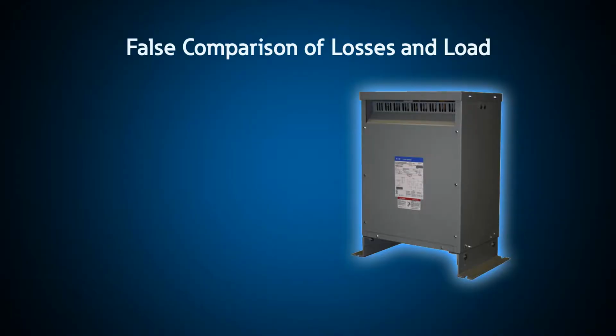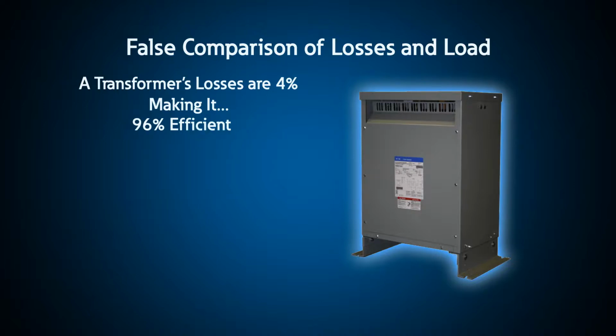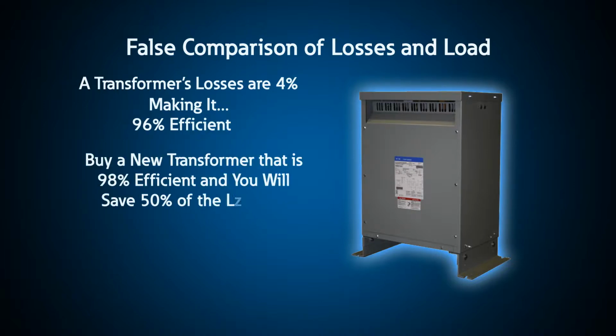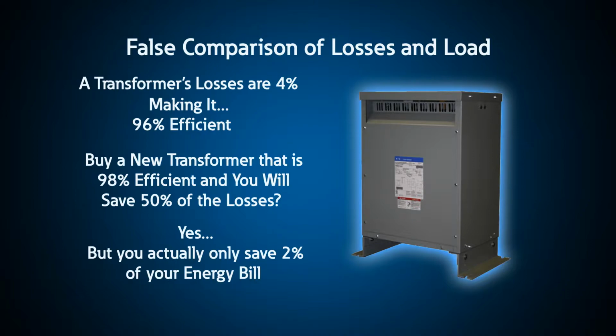Sometimes vendors will use confusing numbers. They may obscure the actual savings by comparing losses and load. For example, if the losses on a transformer are 4%, or the transformer is 96% efficient, you could be advised to install a new transformer that's 98% efficient with the claim that you're saving 50% of the losses. But in reality, you would really only save up to 2% of the actual energy bill.